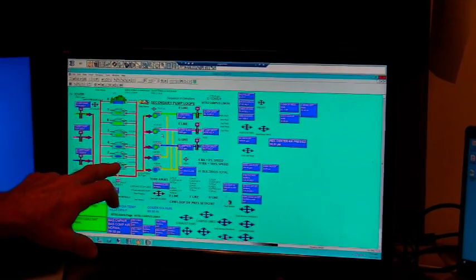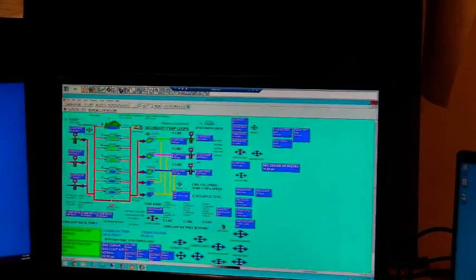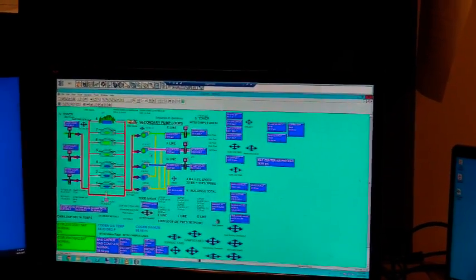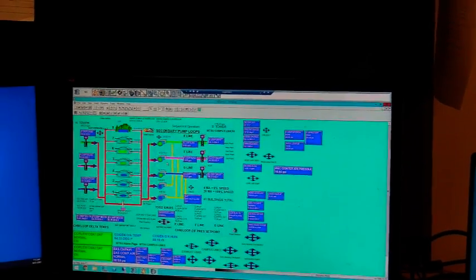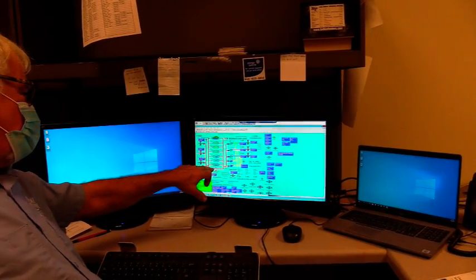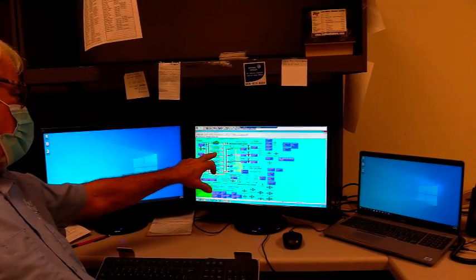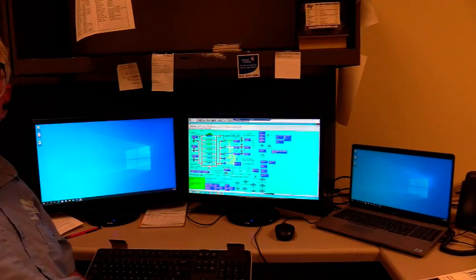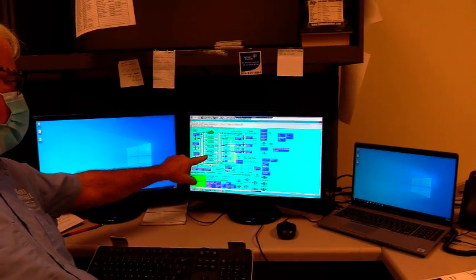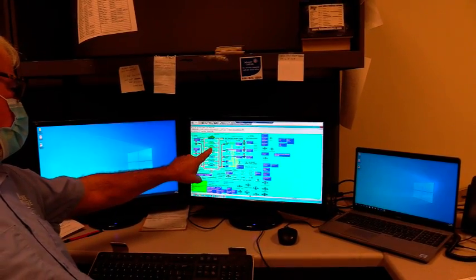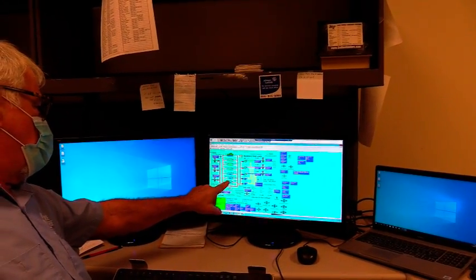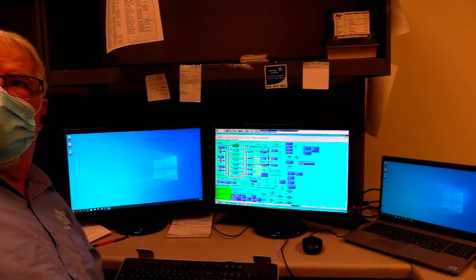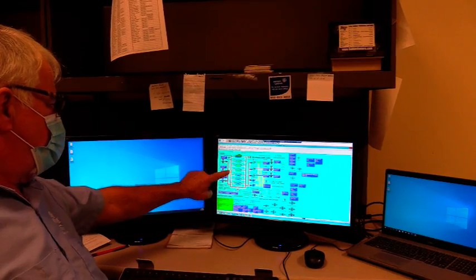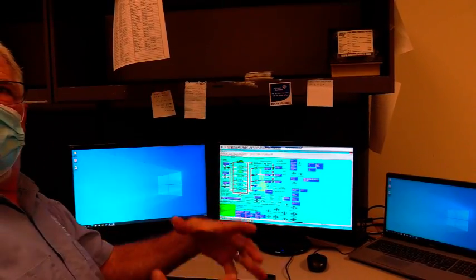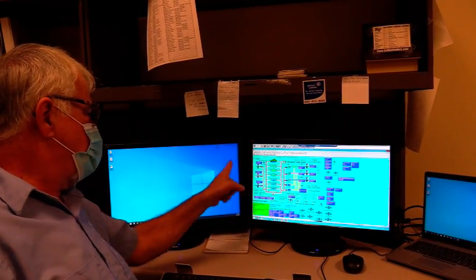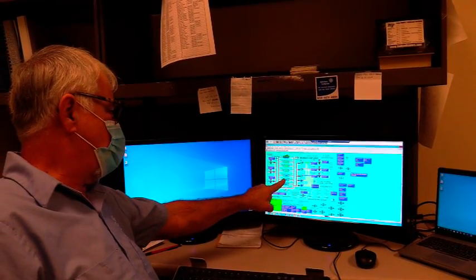The difference is with these chillers, when it's real cold outside you've got to be careful about starting up the low pressure ones, because it can suck the oil out of the compressors. But 4 and 7, they like it cold. So I try to run one of these here, and that way if I need another chiller, I'll crank up 4 or 7, or one on the same tower that shares the same basin. 1 and 2 have a common header between the two cells, but they have the same basin. So if I have one of these going, the water will be warm and it won't be a problem to start up another one.